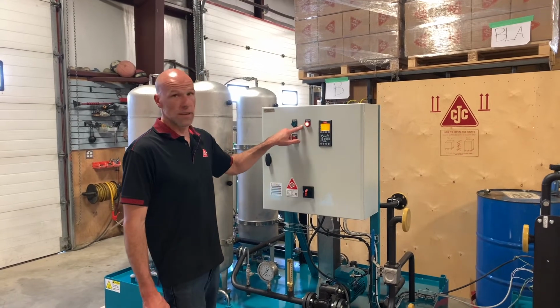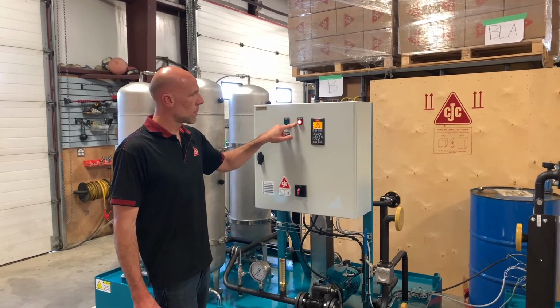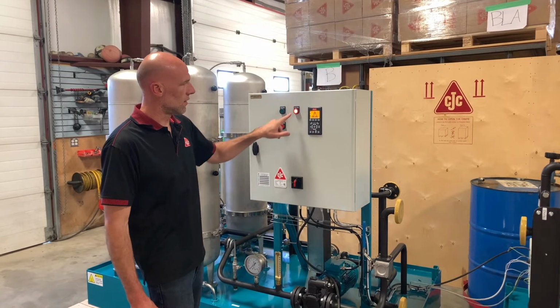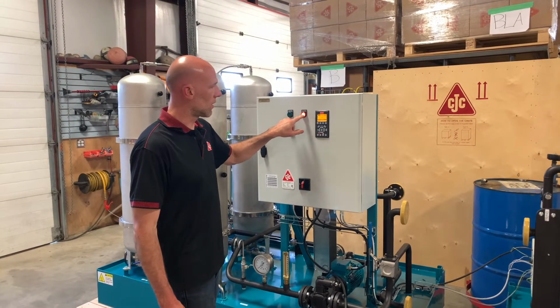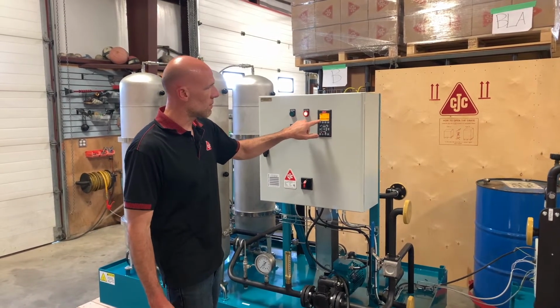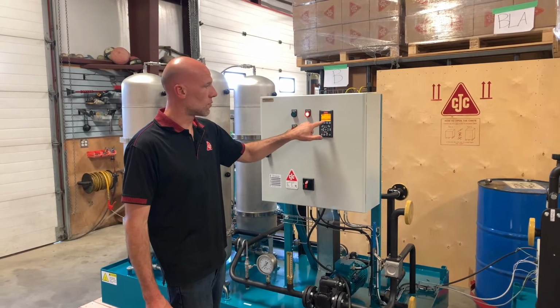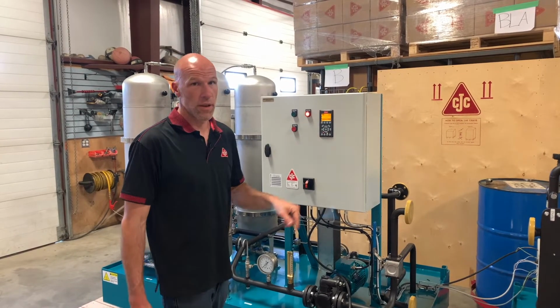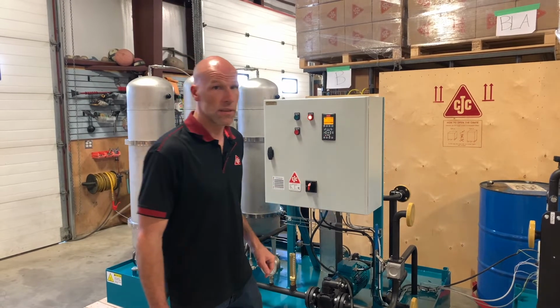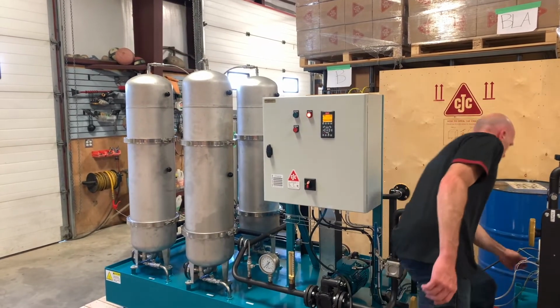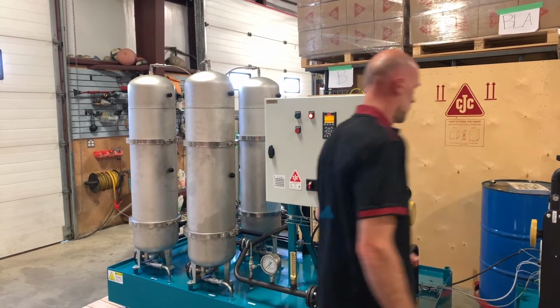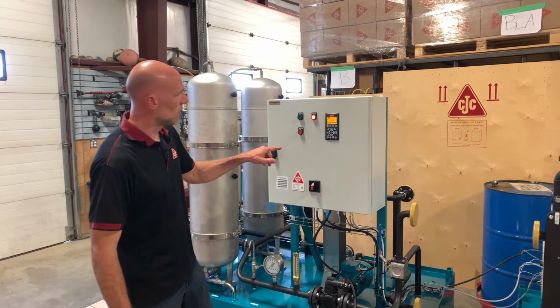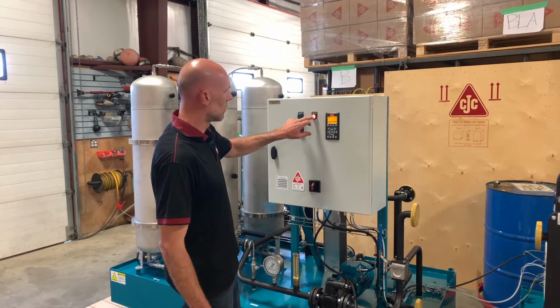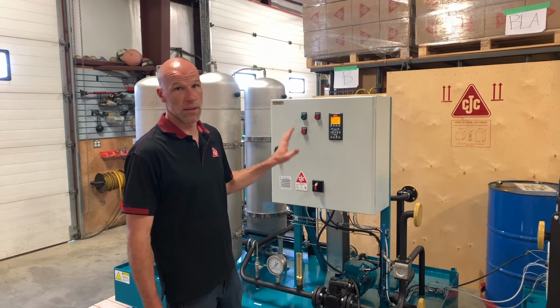First thing you're going to see is this reset light come on, and in this case I can't actually reset it because I've got an alert that you'll probably also see. It says blower not ready. This means that you haven't turned on the other disconnect on the cooling skid. Once that switch has been turned on, you can now reset the alarm and the unit is ready.